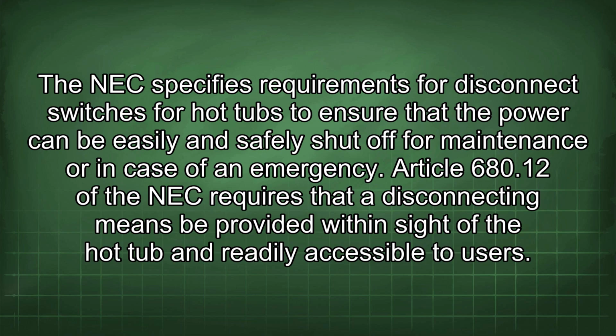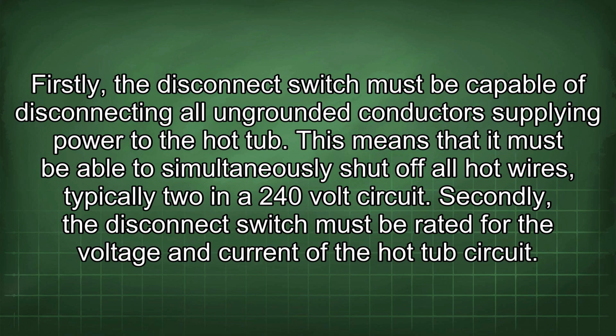The NEC specifies requirements for disconnect switches for hot tubs to ensure that the power can be easily and safely shut off for maintenance or in case of an emergency. Article 680.12 of the NEC requires that a disconnecting means be provided within sight of the hot tub and readily accessible to users. Firstly, the disconnect switch must be capable of disconnecting all ungrounded conductors supplying power to the hot tub. This means that it must be able to simultaneously shut off all hot wires, typically in a 240 volt circuit. Secondly, the disconnect switch must be rated for the voltage and current of the hot tub circuit.